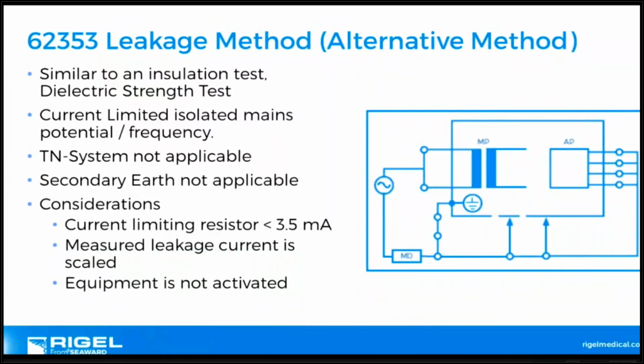method. A frequently asked question is: should I use direct? Should I use differential? Should I use alternative? Some medical equipment manufacturers in the service manuals have various guidance on that. I don't give directives, as I've stressed, but they all have nuances that give solutions that 60601 and the direct method of leakage can overcome. And that is, you can test on secondary earth path systems, stack systems almost, with differential leakage, and you can test on non-TN systems and stack systems using the alternative method.